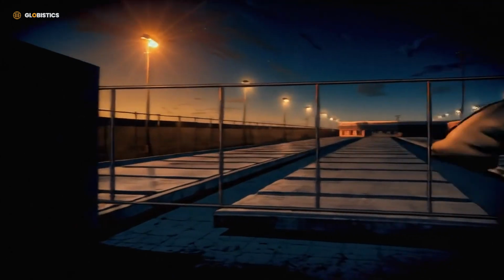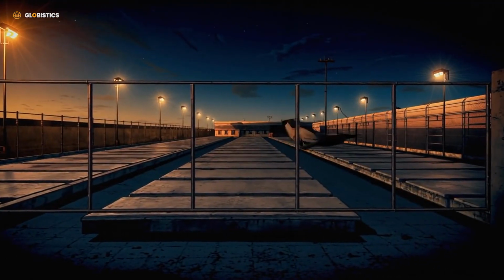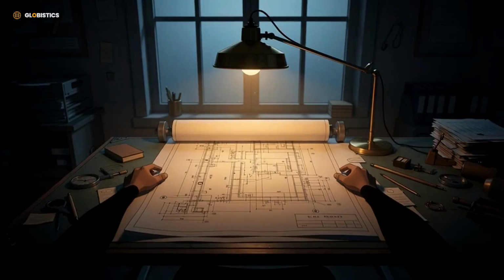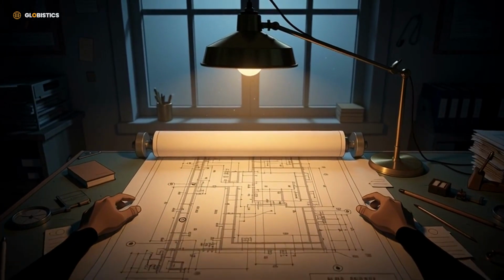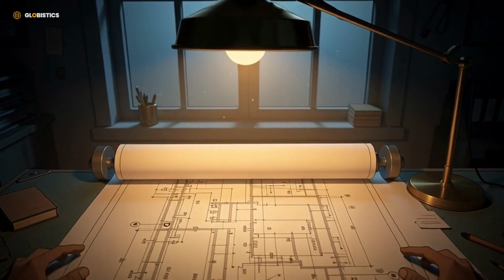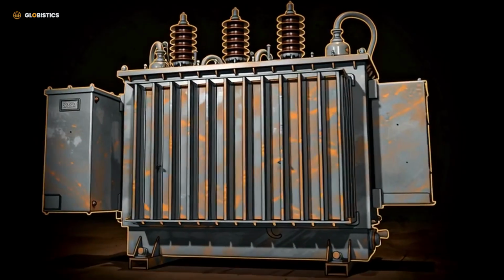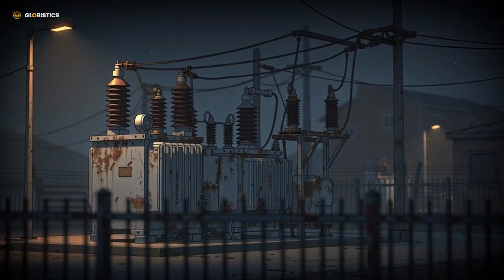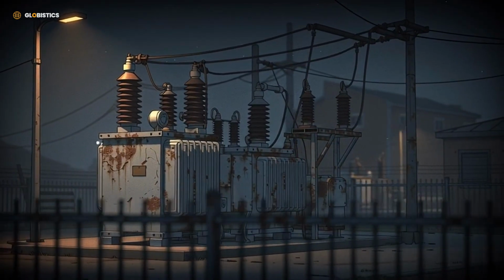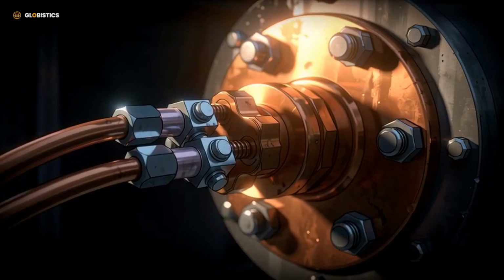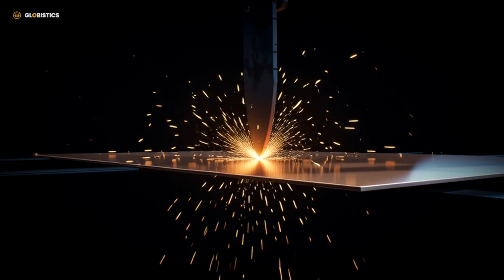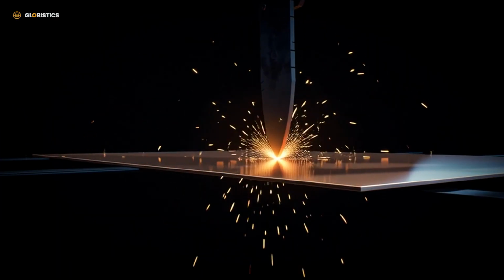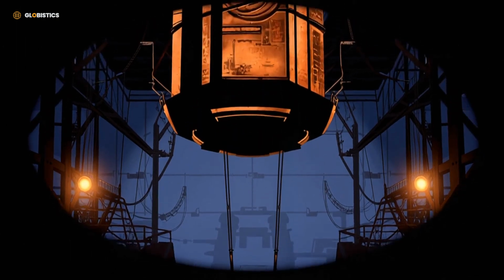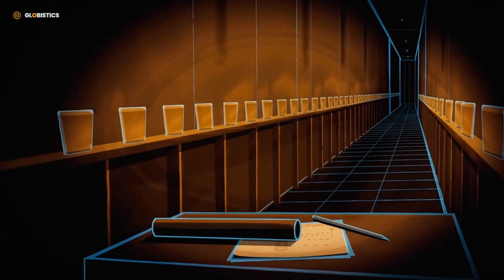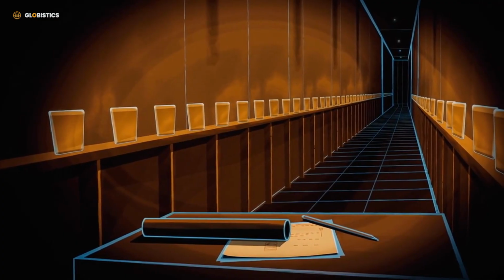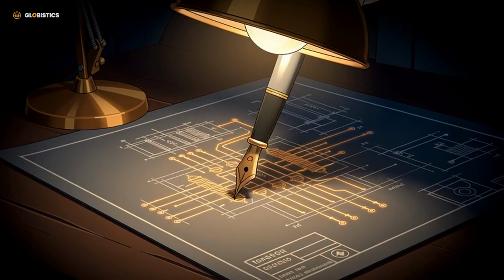There is no shelf, no finished units parked in a yard waiting for a buyer to call. When an order lands, nothing gets picked off a rack, something gets designed. Your unit does not exist until someone builds it. Each unit is engineered for a single substation: its voltage, its footprint, its connections, all fixed before the first sheet of steel is cut. 100 to 400 tons, millions of dollars. This is why money cannot shorten the queue. You are not buying a product, you are commissioning one.